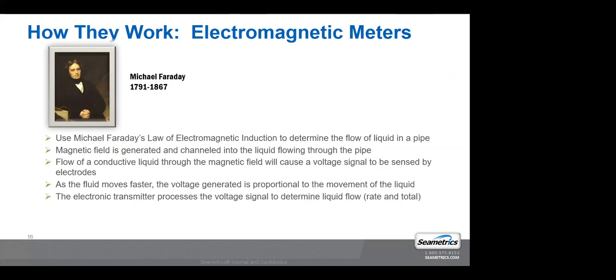Because in the irrigation world, there's a lot of times not power out at the site where the meter's being installed. I know sometimes there is, but a lot of times there's not. These are very rural locations where we're putting a meter in. And in the old days, magnetic flow meters required power in order to operate. And a lot of magnetic meters still do require power to operate. But sometime in the late 1990s, manufacturers started trying battery-powered mag meters.